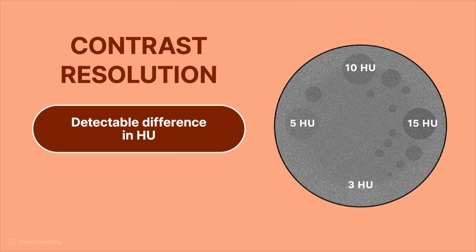In this contrast resolution phantom, the highest level of contrast is 15 Hounsfield units, and the lowest level of contrast is three Hounsfield units.